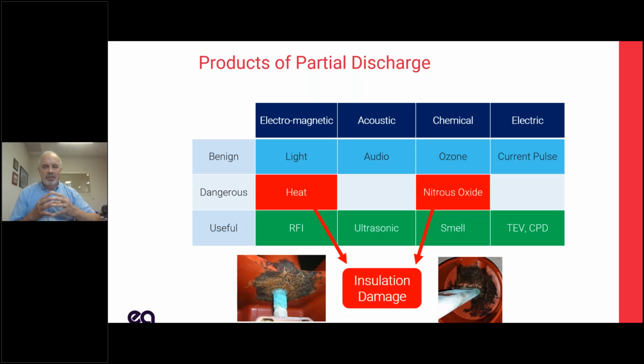And what happens is it creates, from the air molecules, it splits out the oxygen and the nitrogen. The oxygen forms ozone, which you can smell. If you've ever gone into a high voltage substation and you smell ozone indoors, you probably have partial discharge. Nitrous oxide doesn't smell, but it's very corrosive. And by itself, it's not too bad, but when you add any humidity, the nitrous oxide becomes nitric acid, and nitric acid eats through all the insulation we use in the substation.